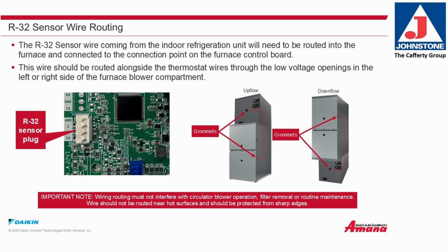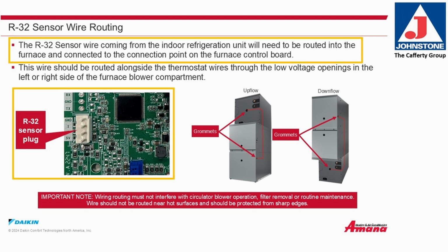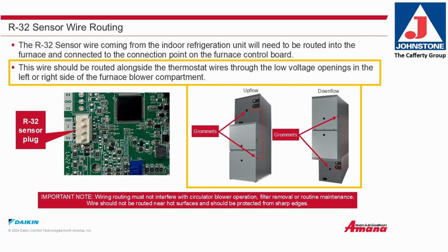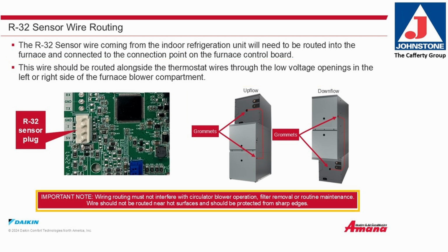R32 sensor wire routing. The R32 sensor wire coming from the indoor refrigeration unit or coil will need to be routed into the furnace and connected to the connection point on the furnace control board. The wire should be routed alongside the thermostat wires through the low voltage openings in the left or right side of the furnace blower compartment. Important note: wire routing must not interfere with the circulation blower operation, filter removal, or routine maintenance. Wires should not be routed near hot surfaces and should be protected from sharp edges.